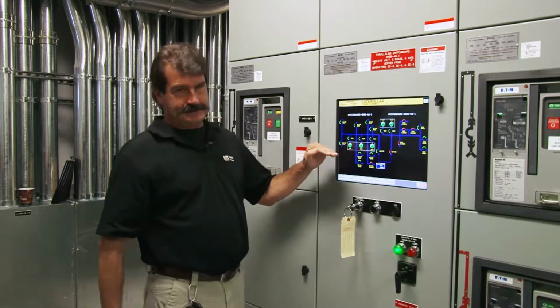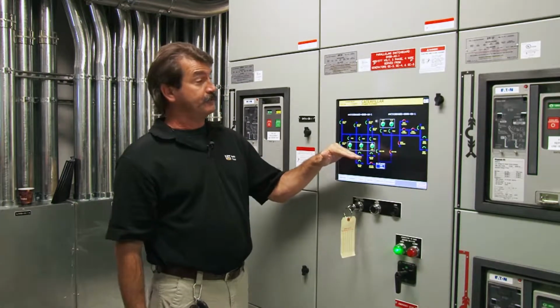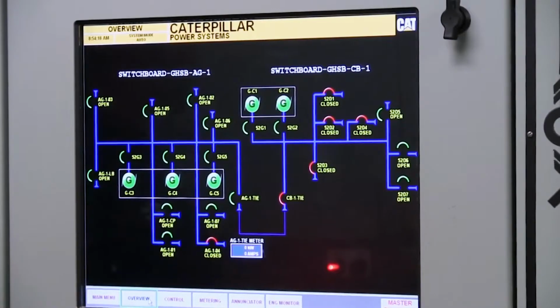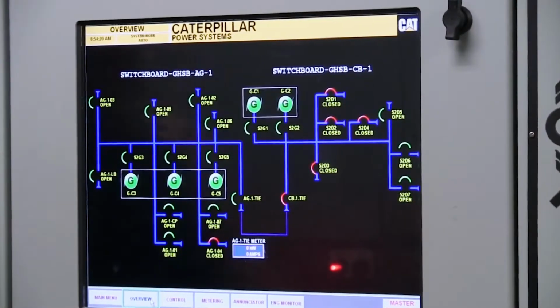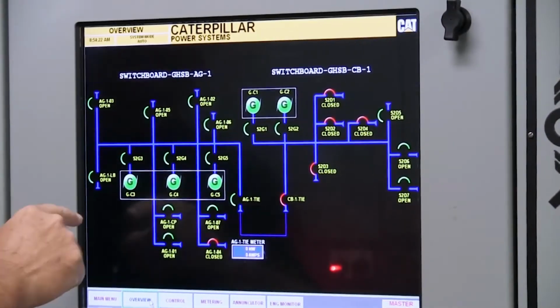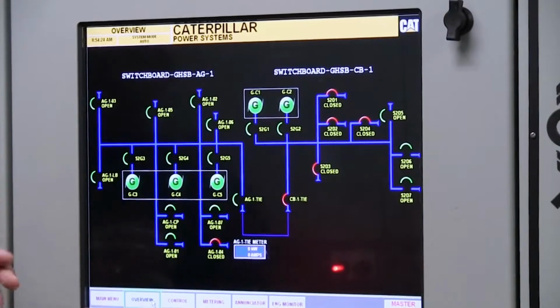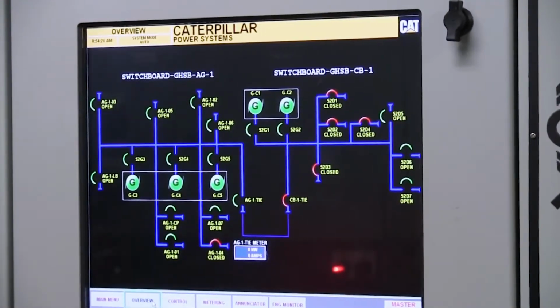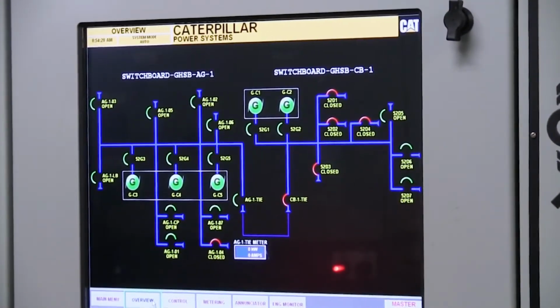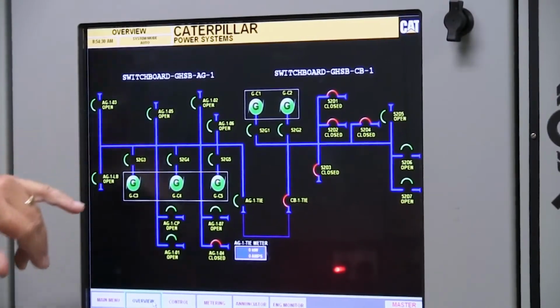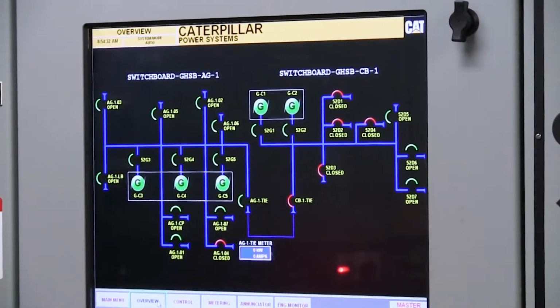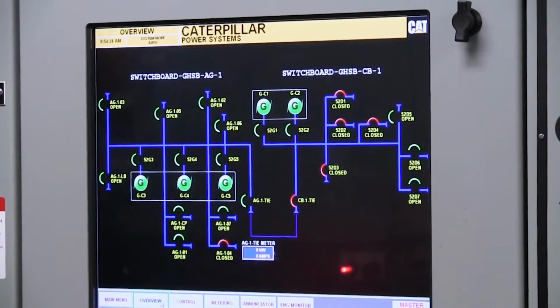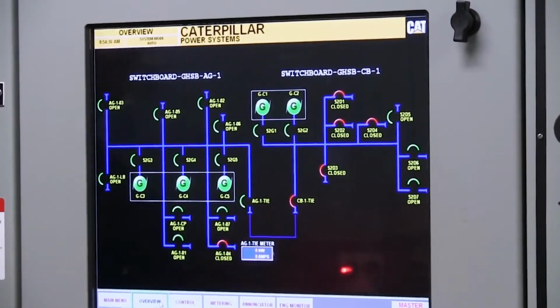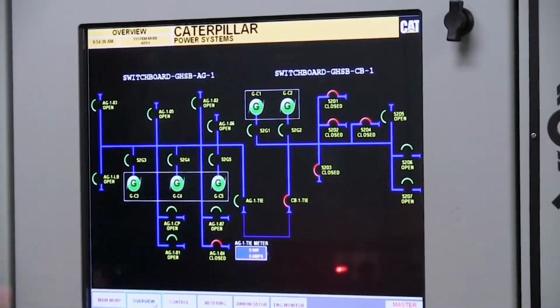But that's in that rare case that you lose all 3 of them on this side, or you lose 2 of them on that side. They'll take care of that. So once the gens come up to speed and synchronize to the bus, your ATSs will see that you have something on the bus, and will close in from there.